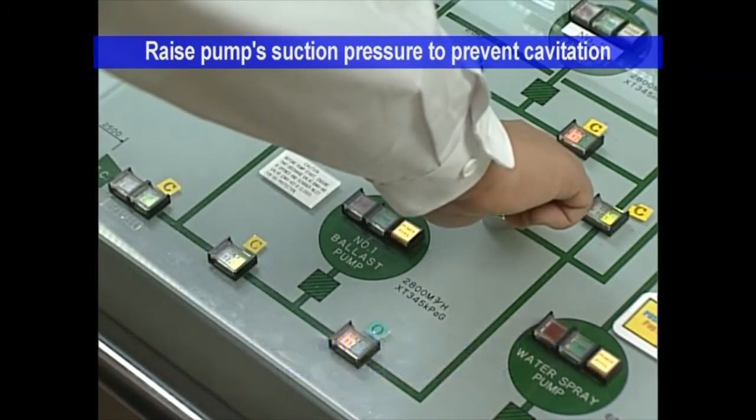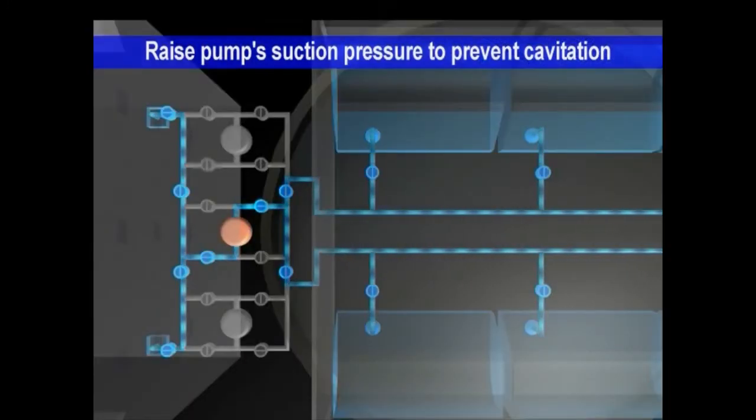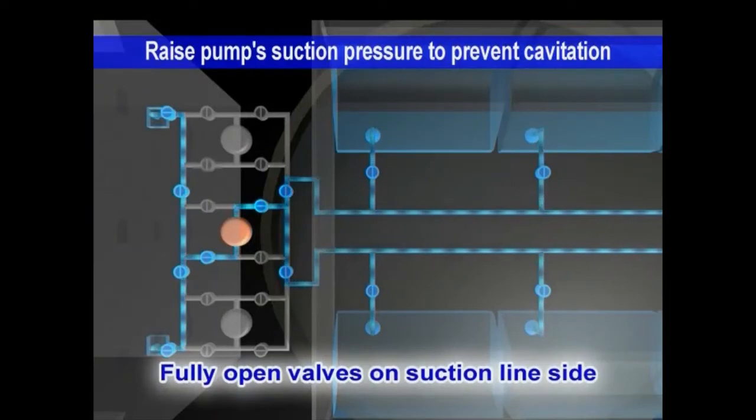To raise the suction pressure, decrease the suction line resistance. With some ships, suction line resistance is decreased by keeping valves on the suction line side fully open at all times. Their opening is not reduced.